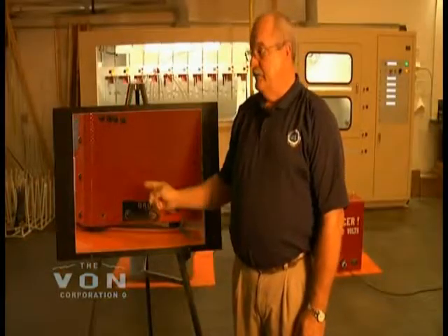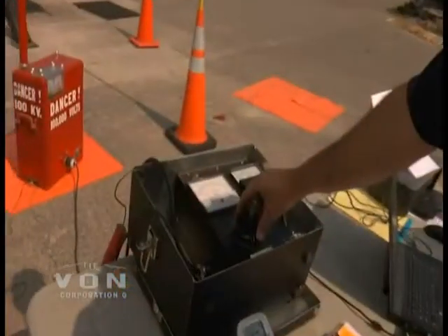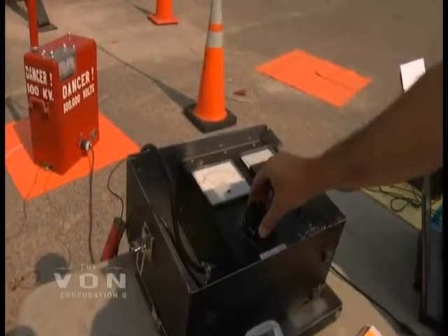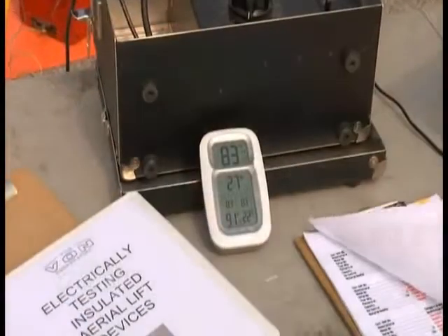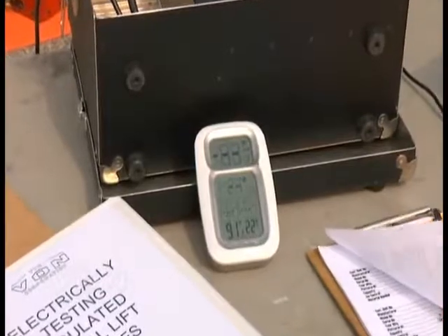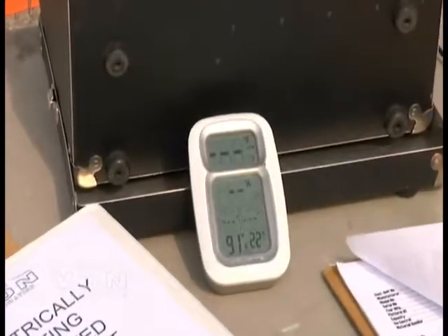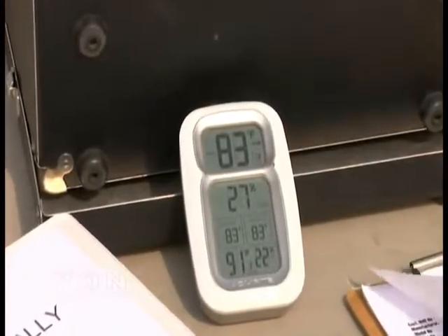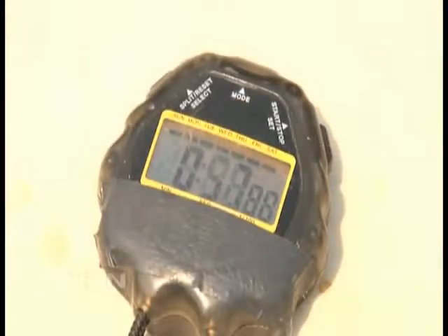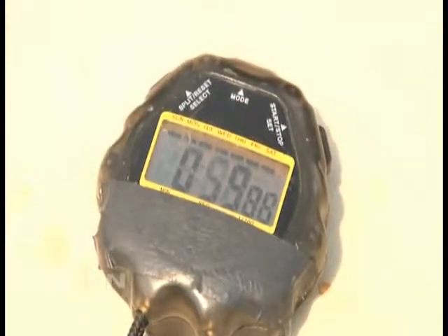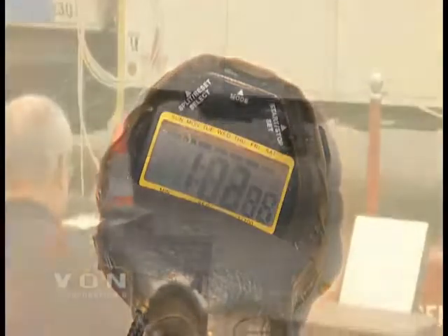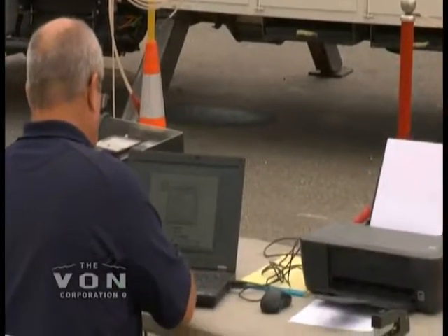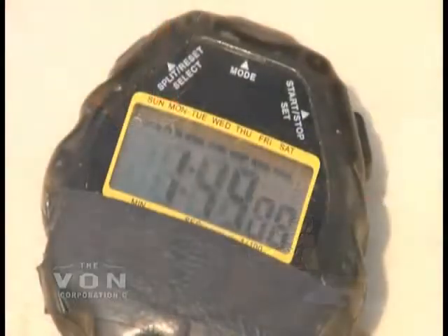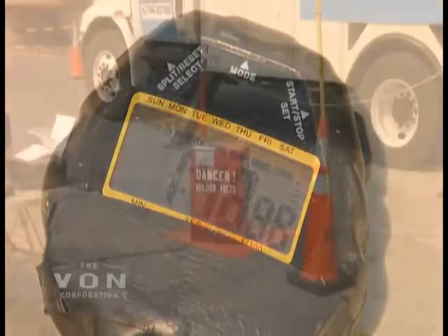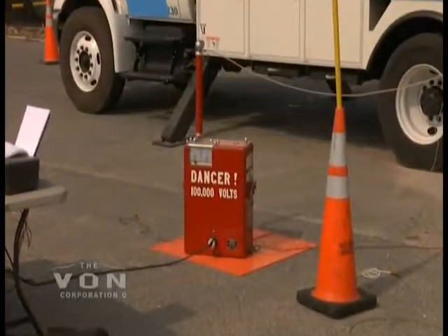We record the temperature and the humidity of each test as we're taking it. This provides us with more information for when our customer asks why their trucks tested better last year than they did this year. Most of that is equated to the humidity in the air. The more humidity, the higher the test readings are going to be. The wind can affect the test readings also a little bit. It'll cause them to go up and down, and that's the reason why we record the humidity and temperature on each test on the trucks.